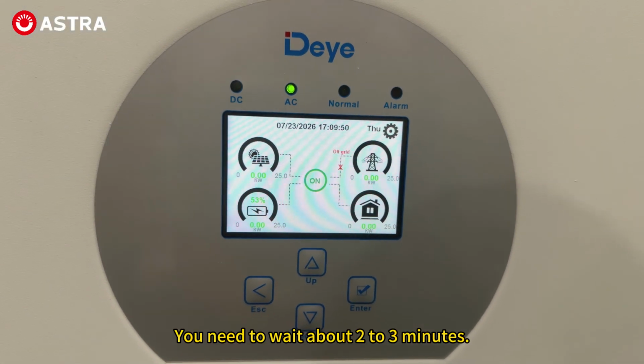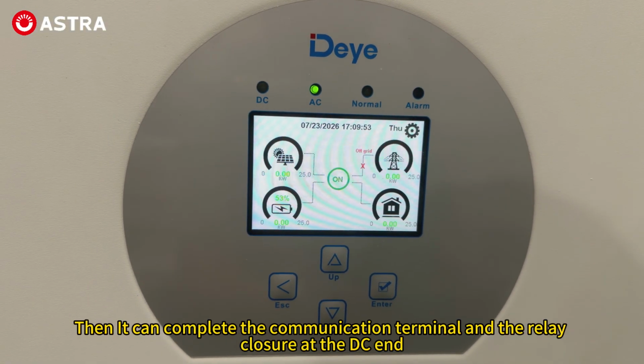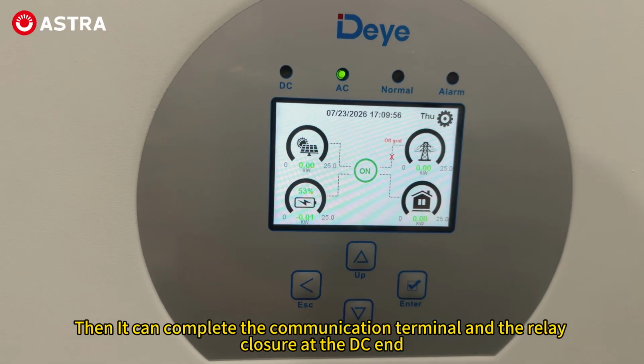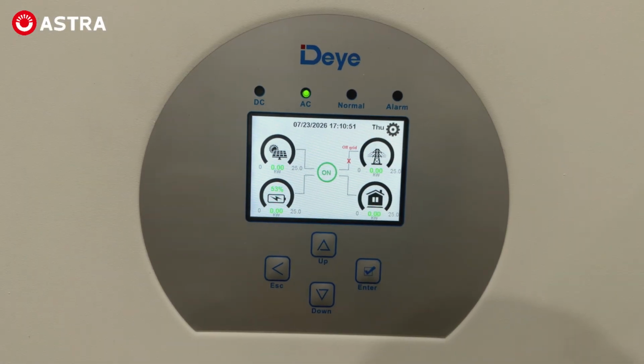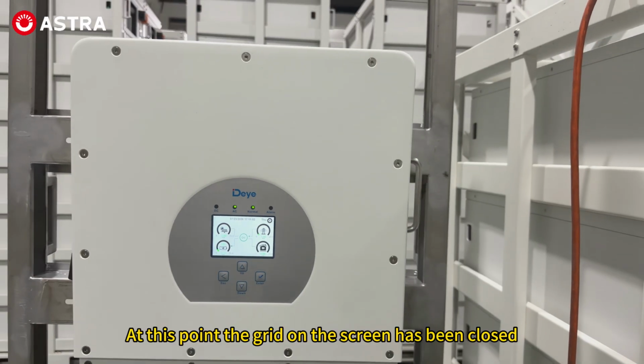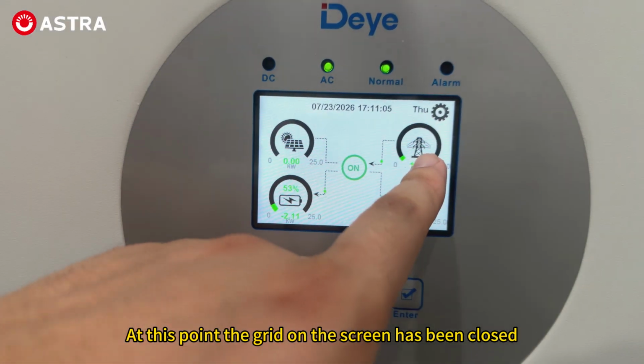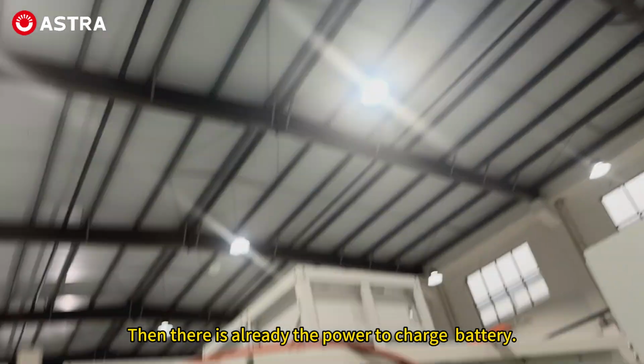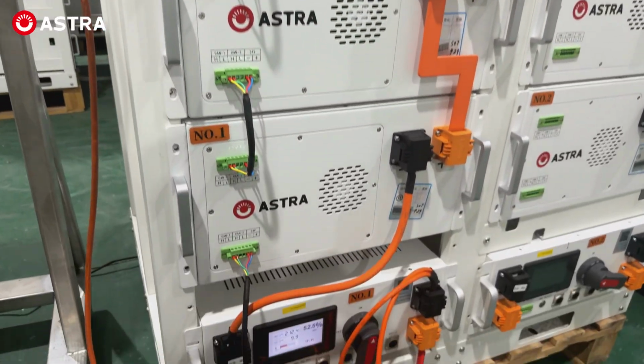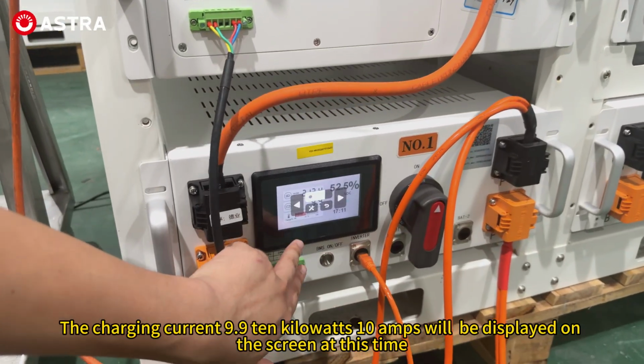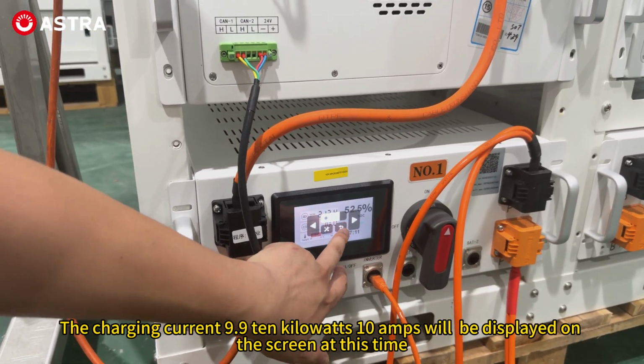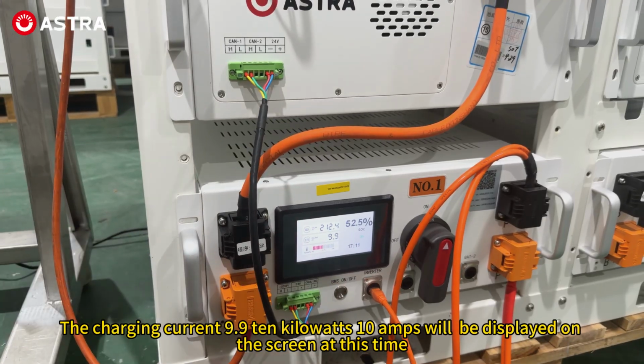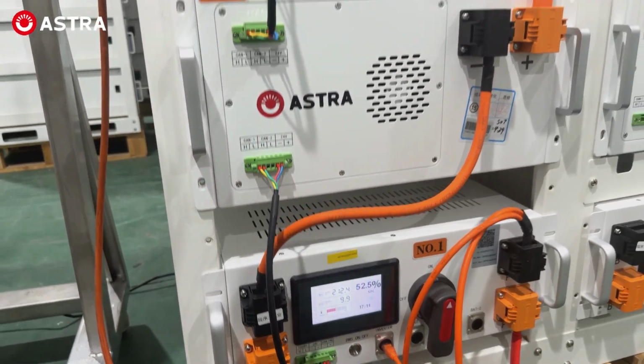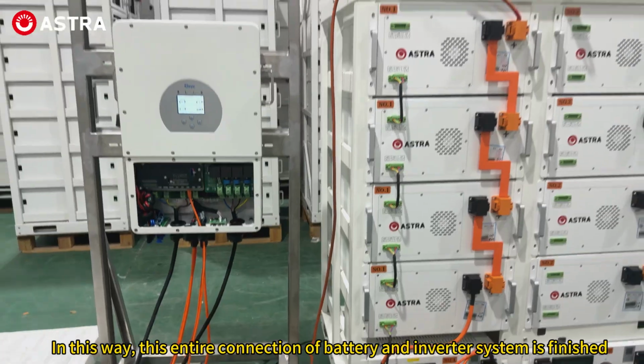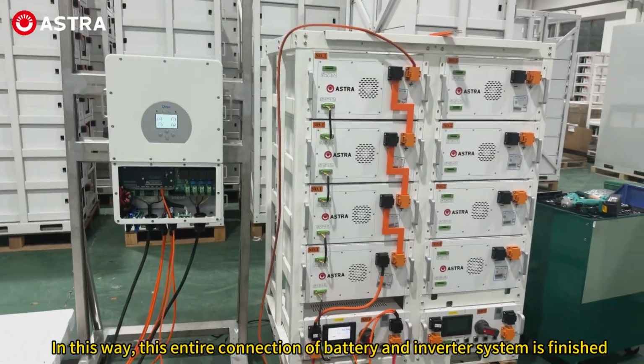You need to wait about 2 to 3 minutes. Then it can complete the communication terminal and the relay closure at the DC end. At this point, the grid on the screen has been closed. Then there is already power to charge the battery. After that, the charging current of 9.9 kilowatts, 10 amps, will be displayed on the screen at this time. In this way, this entire connection of battery and inverter system is finished.